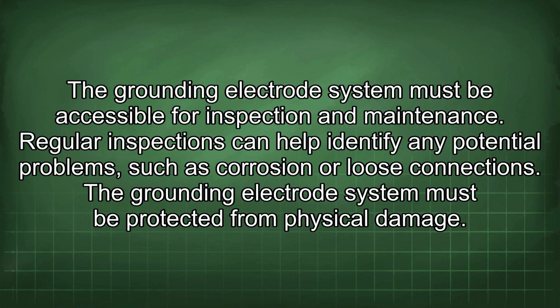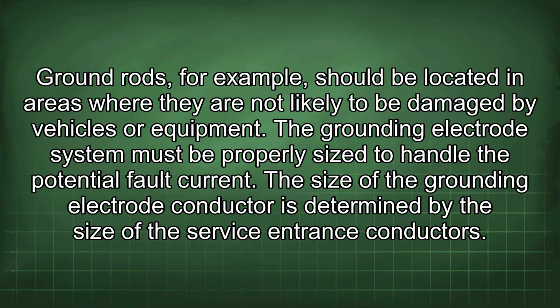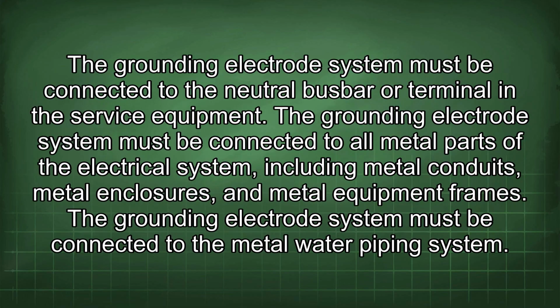Regular inspections can help identify any potential problems, such as corrosion or loose connections. The grounding electrode system must be protected from physical damage. Ground rods, for example, should be located in areas where they are not likely to be damaged by vehicles or equipment. The grounding electrode system must be properly sized to handle the potential fault current. The size of the grounding electrode conductor is determined by the size of the service entrance conductors. The grounding electrode system must be connected to the neutral busbar or terminal in the service equipment.